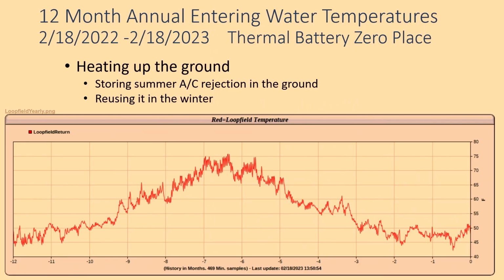So this is about a 64,000 square foot building, and this is the loop field over essentially a 12-month period. So you see in the wintertime, in the summertime, in the wintertime, right there, this is a 12-month period. Then it goes up in the summertime because we take all the heat out of the building. It's called air conditioning. And we do not reject it in the atmosphere. We put it down in the loop field. We store it. And you can see that we're heating up the ground to about 75 degrees. Then we do the opposite. We draw from that thermal battery. And at the end of the year, we are right where we started. It's amazing. We don't even have to use energy or generate energy to recharge a battery. It's a weird concept, right? So it's the thermal battery.